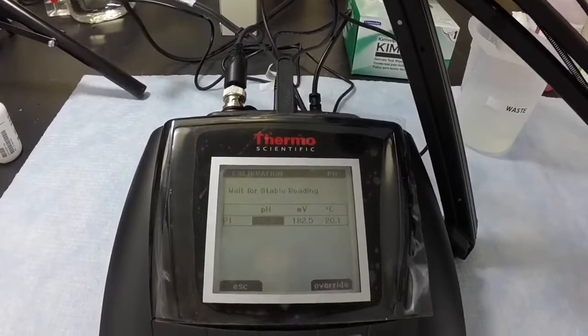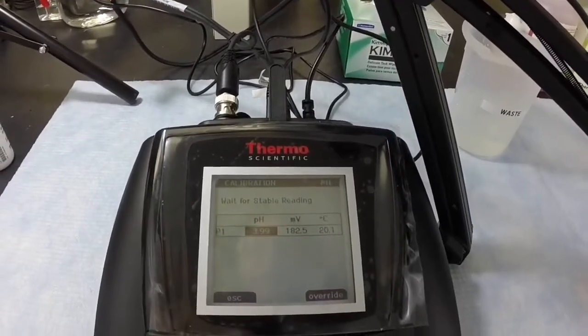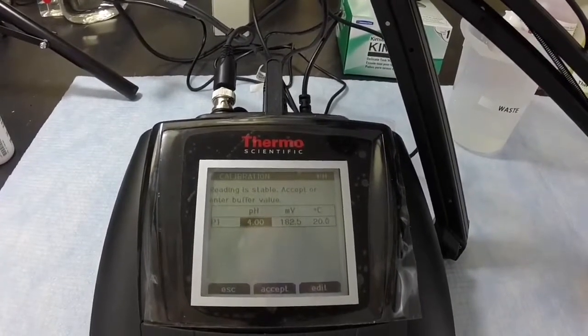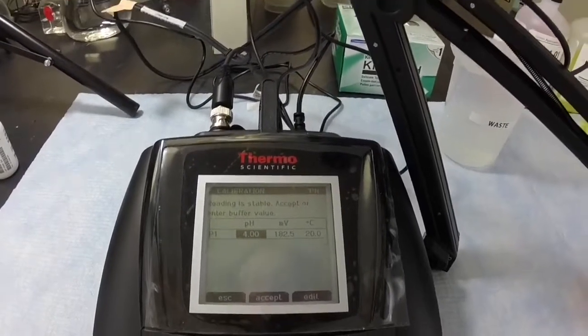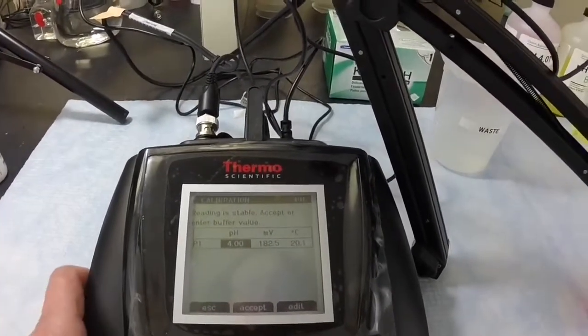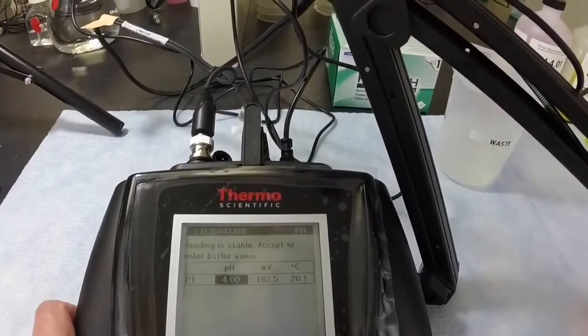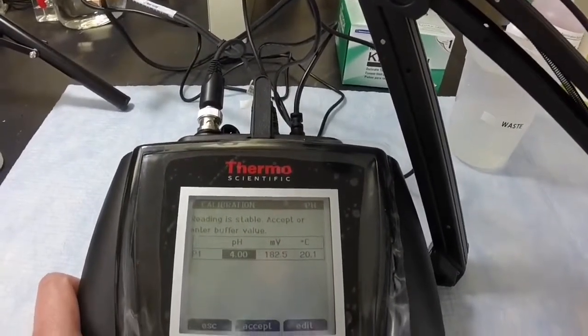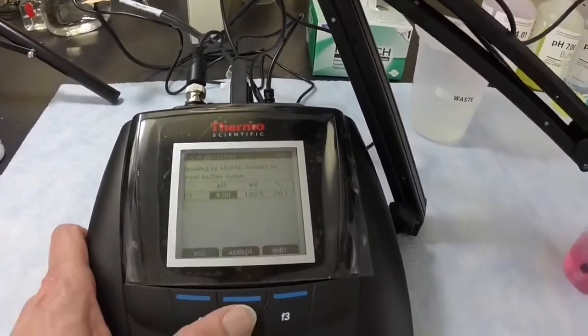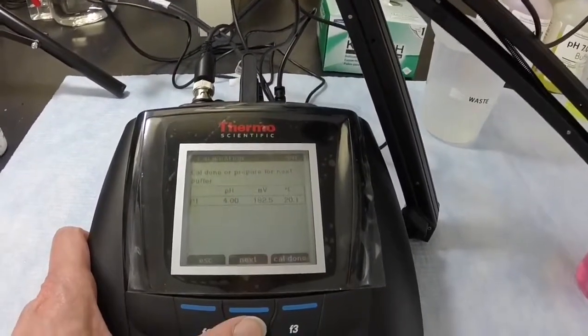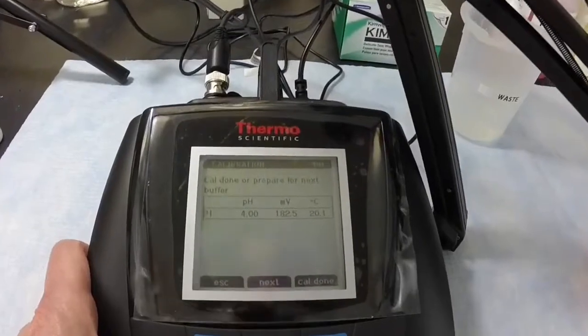When it is stable, it will stop blinking, and the meter will automatically display the correct pH value for the buffer at the temperature measured by your pH electrode or ATC probe, if you're using that. Otherwise, measure the temperature of the buffer and enter that value into the meter before calibration. We press Accept to complete the first calibration point. We press Next to move to the next calibration point.